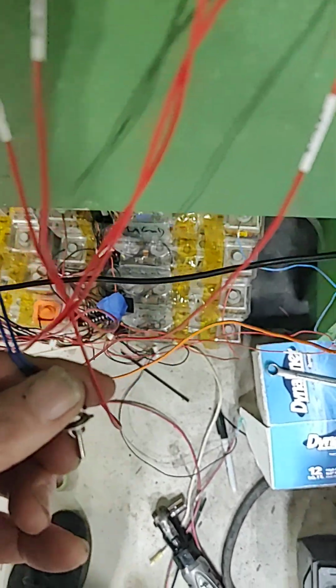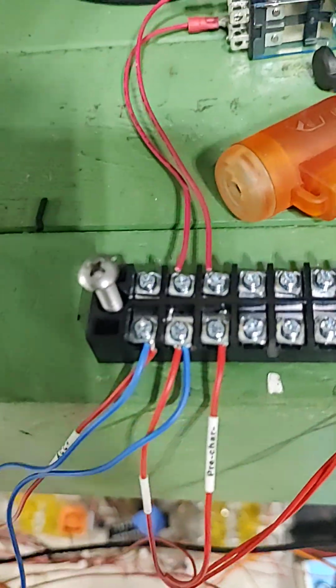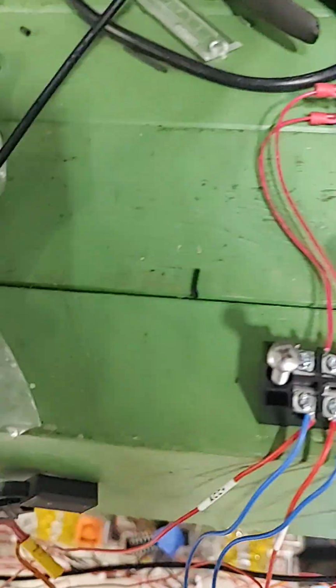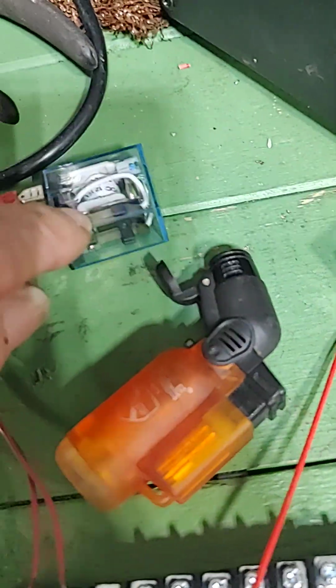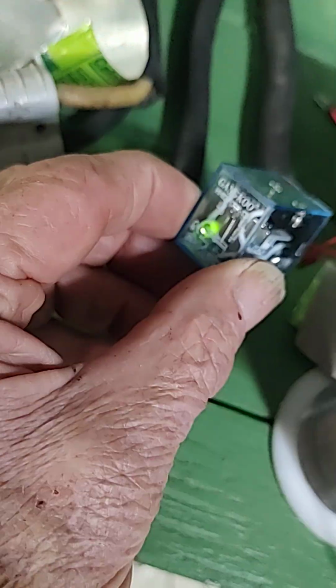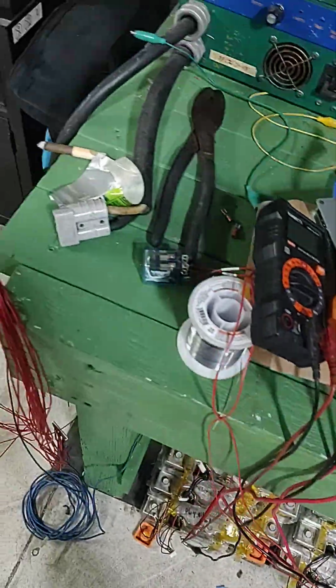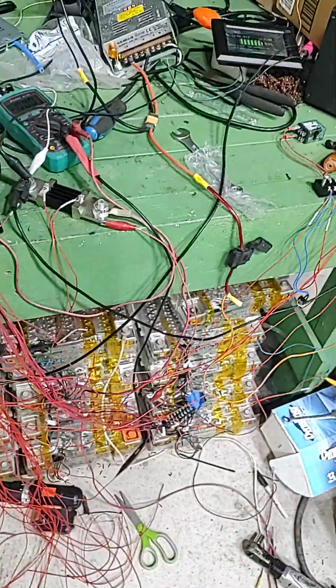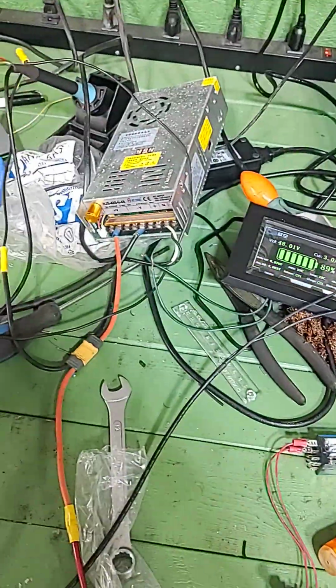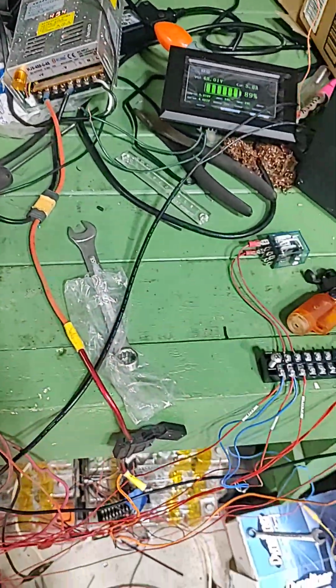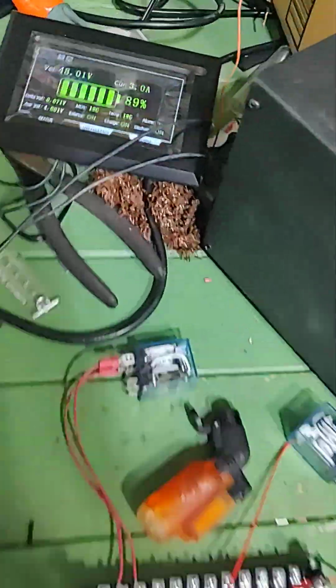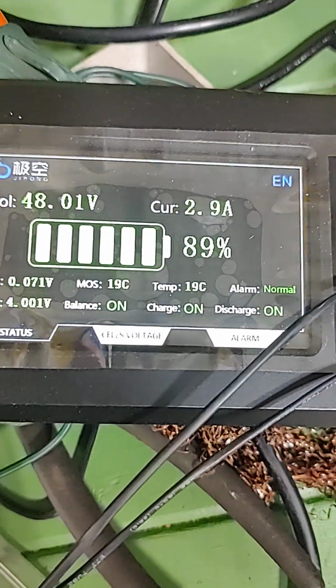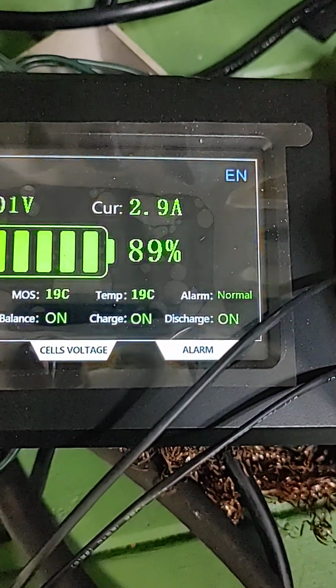So when I hook that to the pre-charge wire, the first thing that happens is our pre-charge engages, and then after a fixed amount of time, our discharge relay engages. So that would be your drive relay, whatever relay you hook up to it. If it's 12 volts, there you go. Now you're driving, and we see on our screen we've got our discharge on.